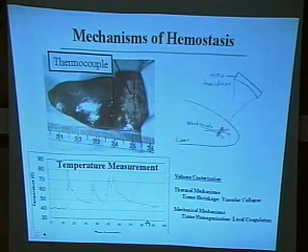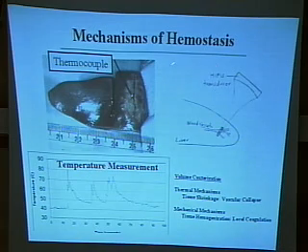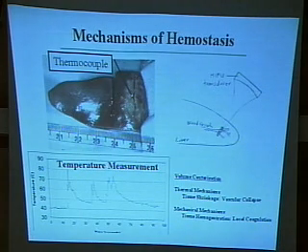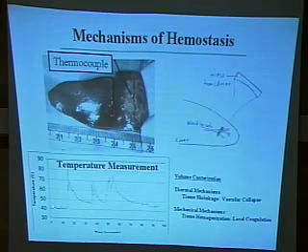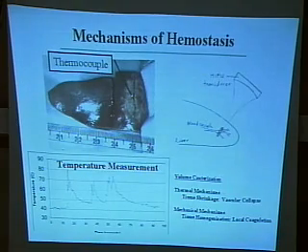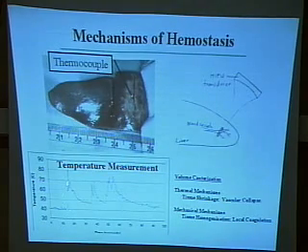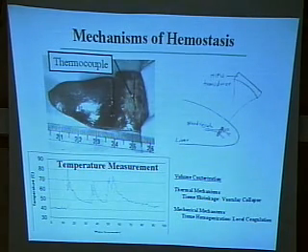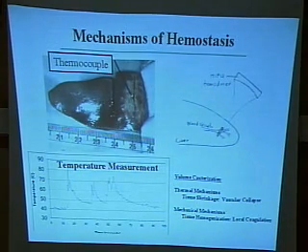So what's the mechanism of hemostasis? Now you'll be able to tell me. It's a thermal effect, right? So we actually tested it. We put a thermocouple in the liver, and then we made an incision right next to the thermocouple. And here's a plot of the temperature measurement as a function of time. We were, of course, scanning across the incision to stop the bleeding from all of the incision site. And you can see every time we passed by the thermocouple, we got a temperature surge of up to about 70 or 80 degrees. And that thermal mechanism cooks the tissue, causes coagulation, causes cautery, basically.